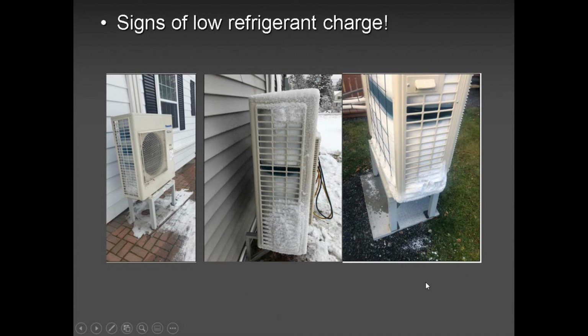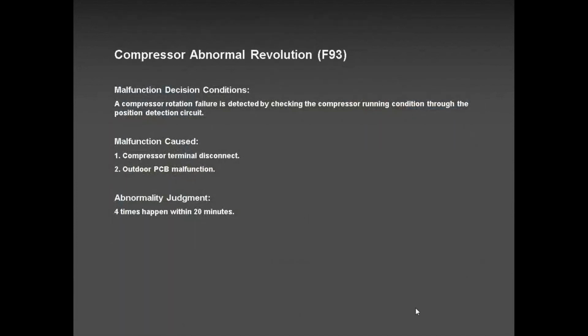The same with the third picture. The system was low on refrigerant. So please, if you see this kind of pictures, rest assured that the unit did go into defrost cycle, but got terminated too early. Okay? So if you have a scenario like this on a multi-zone, definitely you are low on refrigerant. And if you paid attention to the picture I showed on the single zone, at the bottom there was a lot of frost. That would be another case.